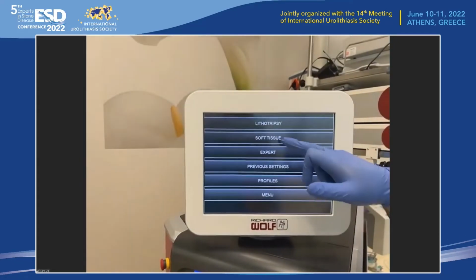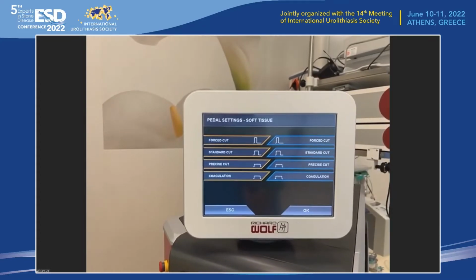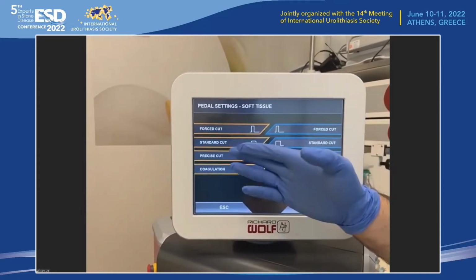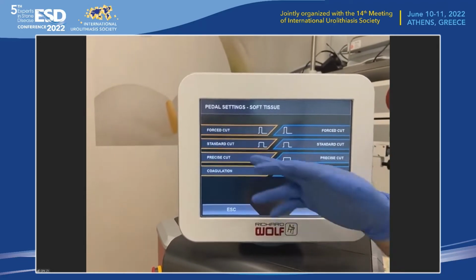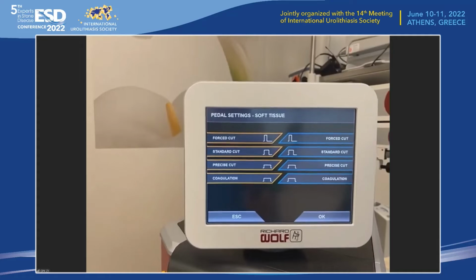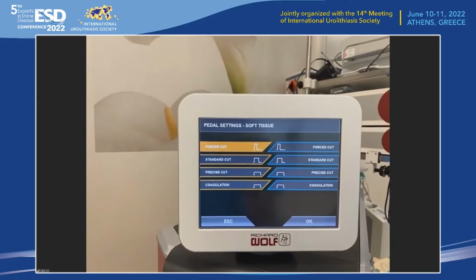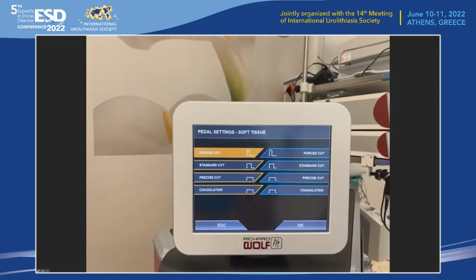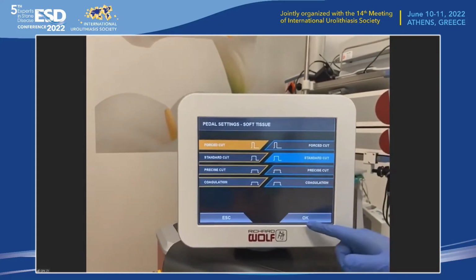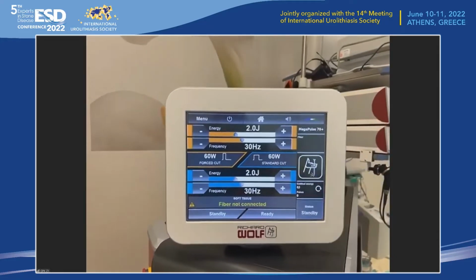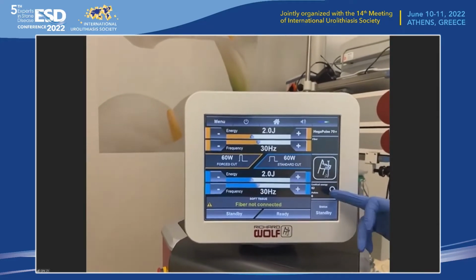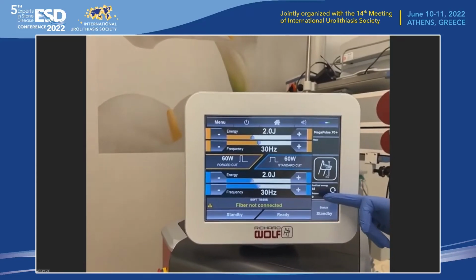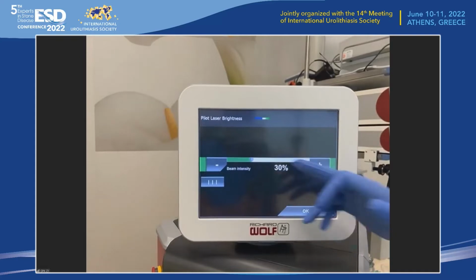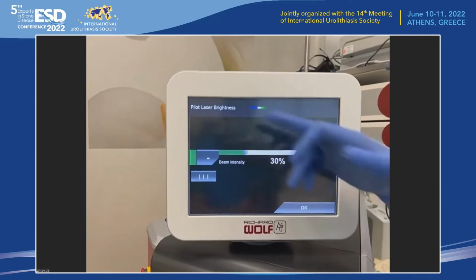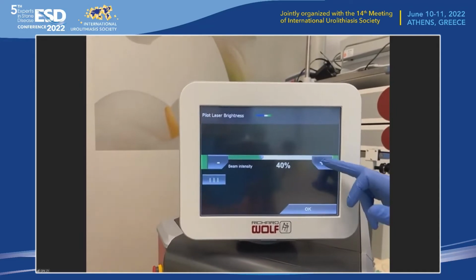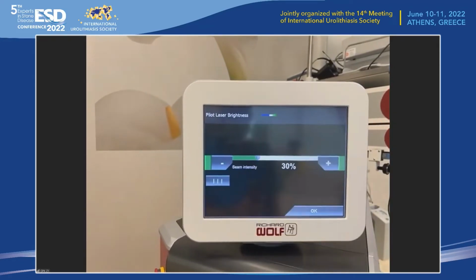So at the end, you can go to soft tissue, the same procedure here. We have different cutting modes with force cut, standard cut, precise cut, and coagulation. Same here, like lithotripsy, you can choose two different settings for your foot switch. For example, force cut and standard cut. Then you just push OK. And here we are ready for the OR mode. Here you can see the emitted energy, the pulses, and you can also change the pilot laser brightness from 30% to 40, 50, or you can reduce it.